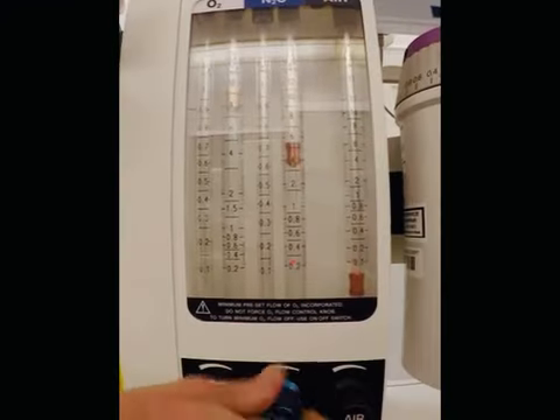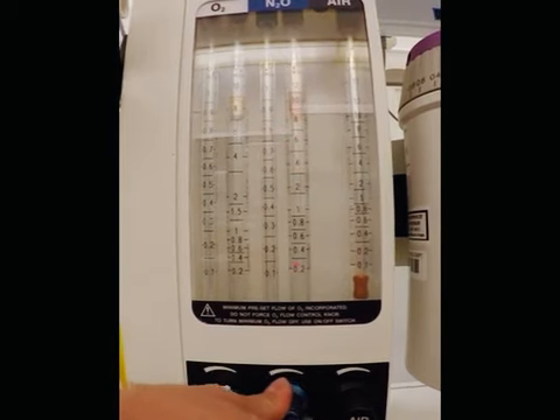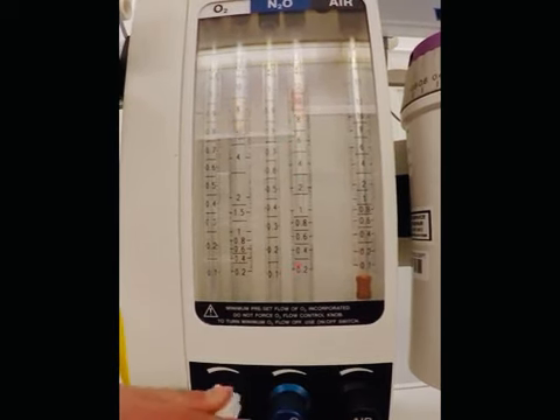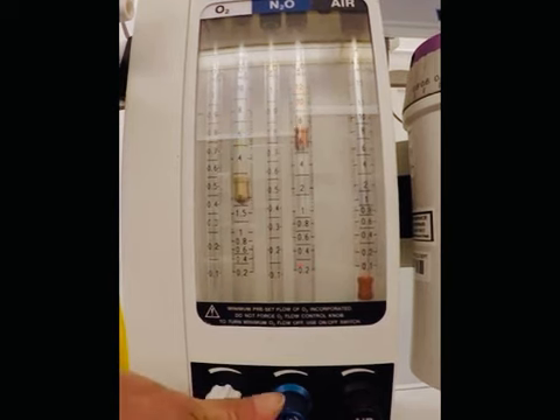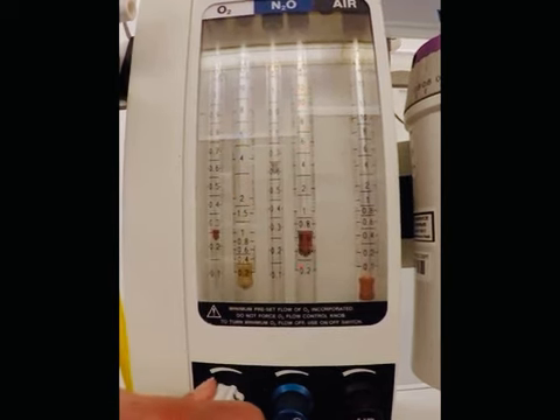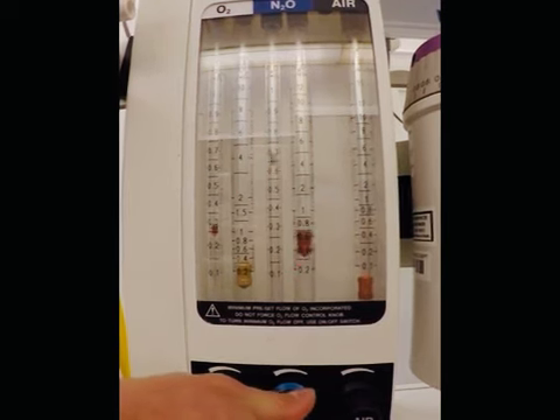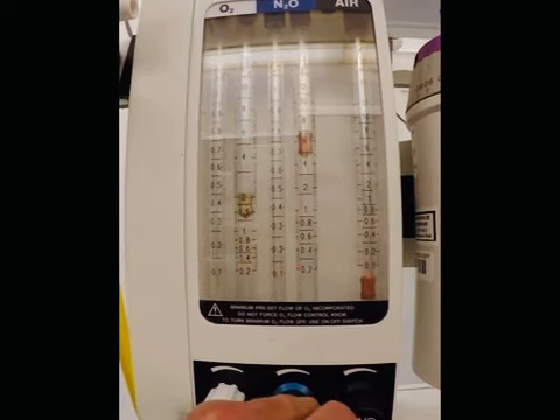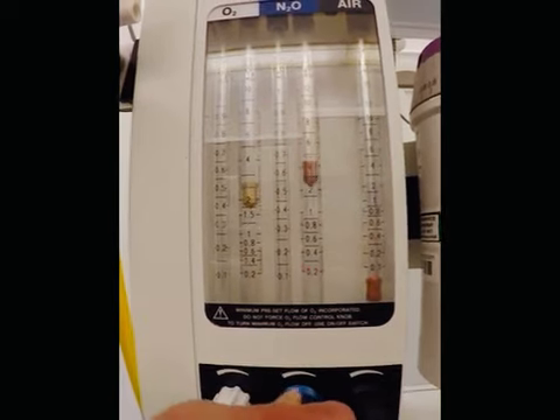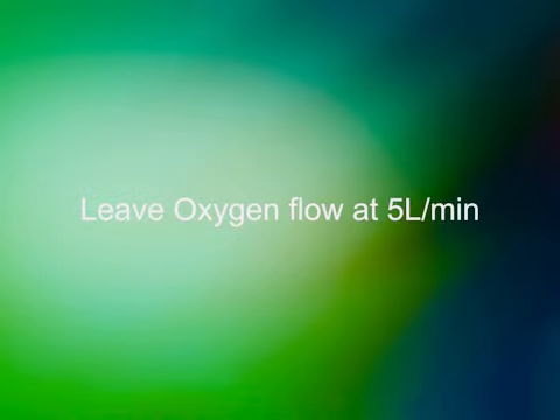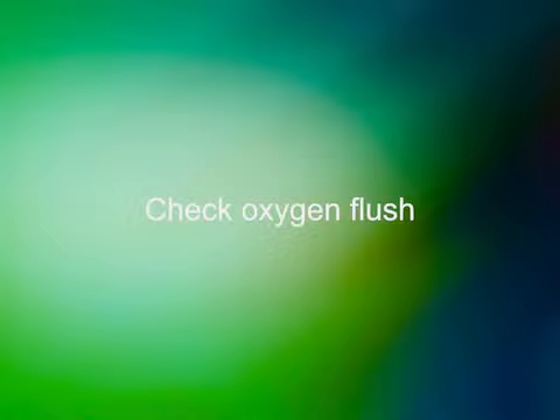Then check the hypoxic guard is working, ensuring that a hypoxic mixture cannot be delivered to the patient. This is done by checking that the nitrous level drops as you turn off the oxygen and that the oxygen automatically comes on when turning on the nitrous. You may also note the oxygen flow meter never fully turns off and always delivers a minimum of 0.3 litres per minute. You can then leave the oxygen on 5 litres per minute for the remainder of the anaesthetic machine check. Check that the oxygen emergency flush is active.